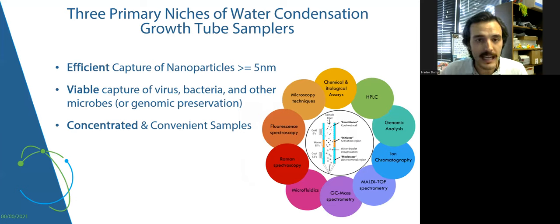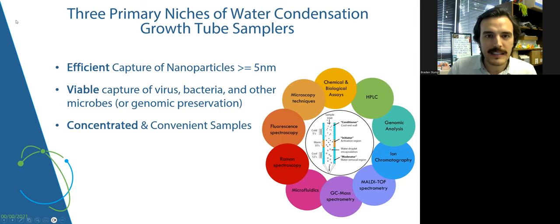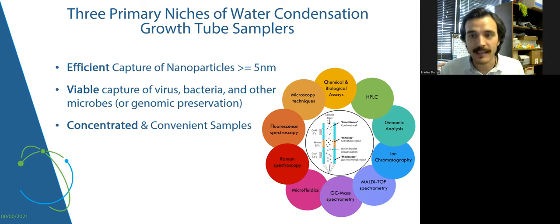The water condensation growth tube sampling technique that Aerosol Devices manufactures and licenses has three primary niches — three primary abilities that make it competitive compared to other technologies. The first of those three is efficient capture of nanoparticles, greater than or equal to five nanometers. The real range of particles we can sample across is from five nanometers to 10 microns — a very wide range, all with effectively even and high collection efficiency. You don't see a lot of more traditional techniques being able to sample into this low of the nanoparticle range with that high efficiency, which is useful not only in the bioaerosol world but in the semiconductor industry and in aerosol science and aerosol chemistry.